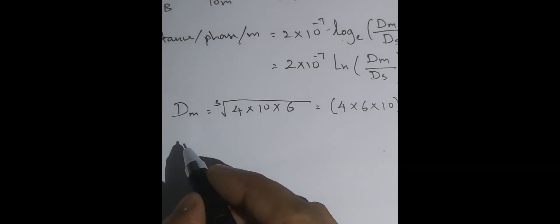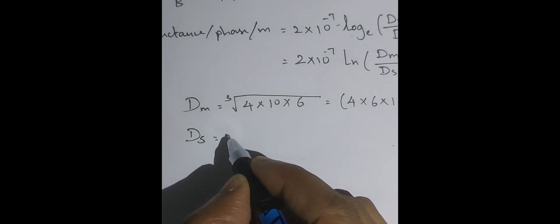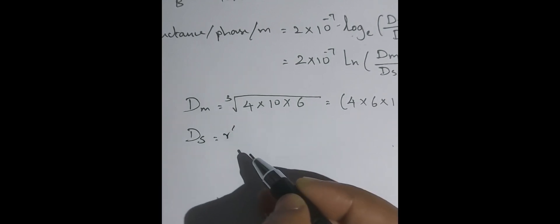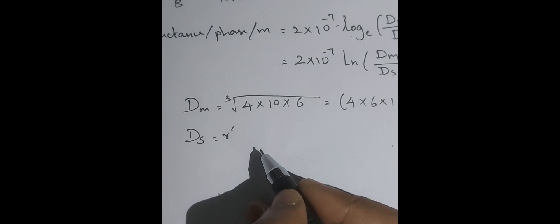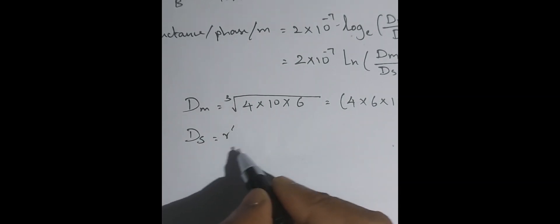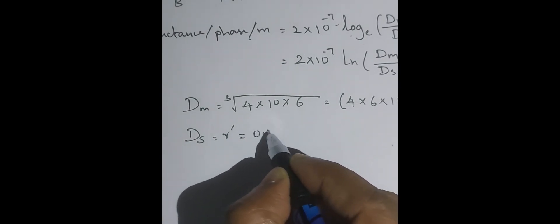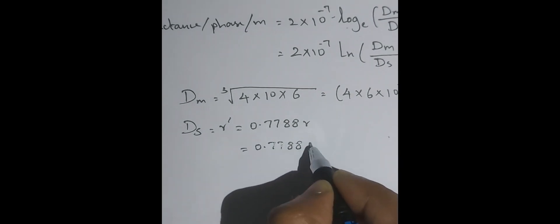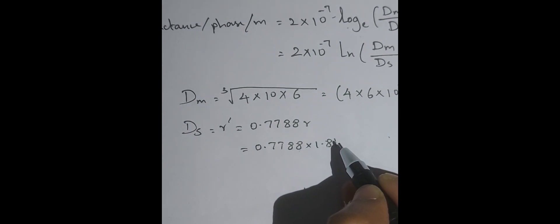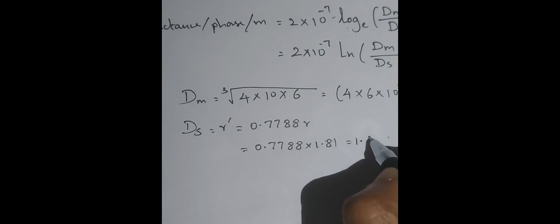Next we have to find ds. In this case, ds is nothing but r dash, because each phase has only a single conductor. r dash equals 0.7788 × r. So r dash equals 0.7788 × 1.81 centimeter, which gives 1.41 centimeter.